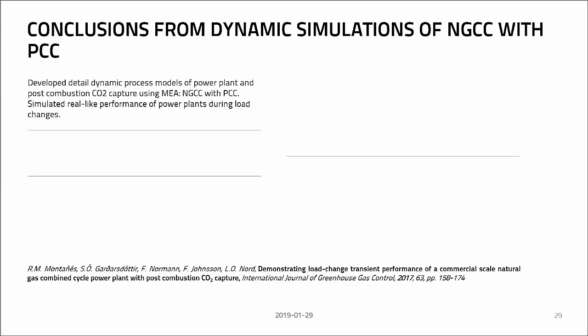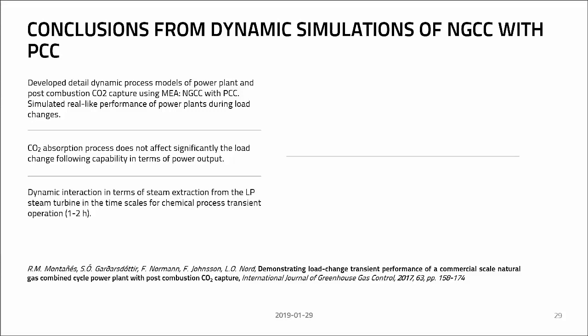So, some conclusions from these dynamic simulation studies. First of all, we managed to develop detailed dynamic process models of both the power plant and the capture unit and simulate the real-life performance of the power plants during load changes. One of the first conclusions is that the CO2 absorption process does not significantly affect the load change following capability in terms of power output from the power plant, but there might be some small amplitude dynamic interactions in terms of steam extraction from the low pressure steam turbine. And that means that the extraction might be oscillating for around 1 to 2 hours.